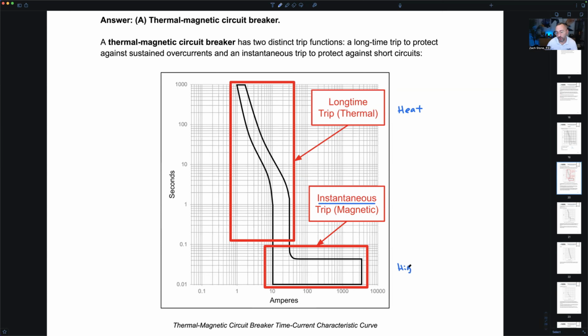This is for protecting against short circuits. We want it to trip as soon as possible, with as minimal delay as possible, because we've got a really high fault current. So the longer it persists, the more damage occurs. When I say long, I'm talking about in terms of cycles, which are a blink of an eye in terms of a human sense of time. So the instantaneous trip, the magnetic region, we want it to pop right away.